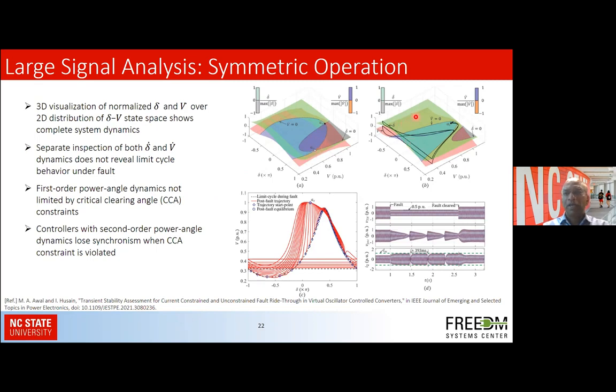And then when it enters the fault mode, you see there is no point of intersection. This is one of the scenarios presented both through simulation and experiments, where under fault it enters the limit cycle mode. But through this assessment, plotting this in a 2D fashion, we can show that under fault, from wherever you start returning from the fault mode to the regular mode, it goes into this stable operating mode, even though you are in this limit cycle scenario. So once you enter the fault and then the fault is cleared, it's able to come back to this stable situation. The key message here is that first order power angle dynamics is not limited by the critical clearing angle constraints, which it is where the controllers have second order power angle dynamics.